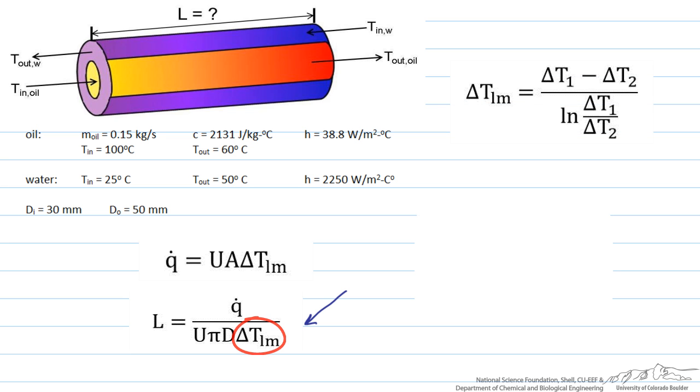Delta T log mean is going to be our delta T1, which refers to the difference in temperature at the entrance of the heat exchanger, minus our delta T2, which is the delta T at the end of the heat exchanger, divided by the natural log of delta T1 over delta T2.